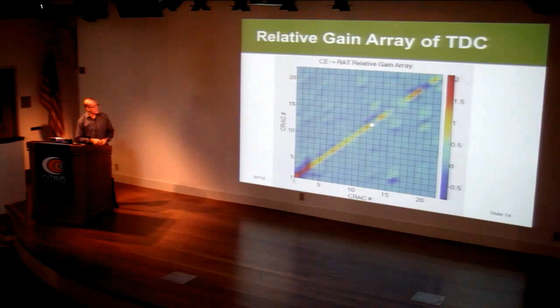So this is a graphic of that data center I showed you with the 22 air conditioners. It's a visual of the relative gain array. You can see this kind of teal color is 0, blues are less than 0, and the diagonal, like I said, is what matters. Here you can see we have less than 0 there, and some close to zero here and here. If you look at the numerical values, the minimum diagonal is less than 0, minus 0.3. We have 4 of them that are less than 0.5. And the result is that this system with return air control is unstable.